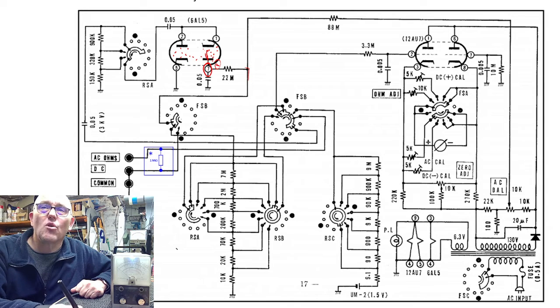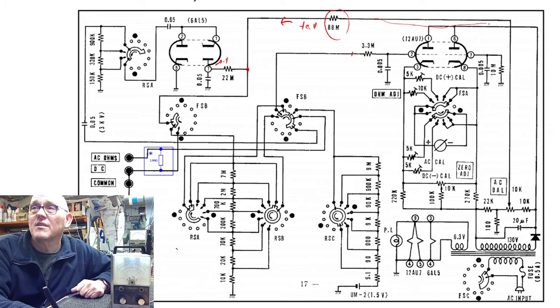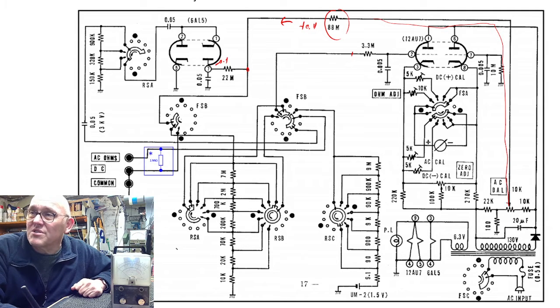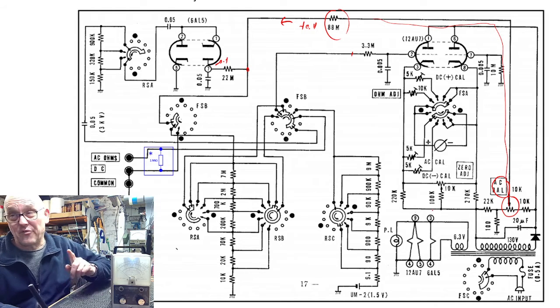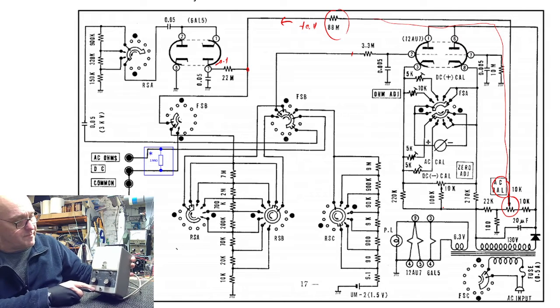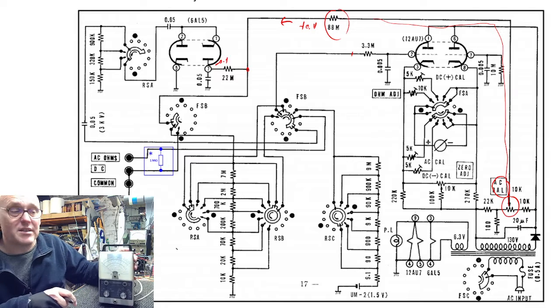So we need to offset that bit of negative voltage when there's zero input. Let's say that it's minus 0.1 volts. If we don't want to put minus 0.1 volts over here, we're going to have to offset it. So we're going to have to put plus 0.1 volts over here. And the way that it's done is through this 88 mega ohm resistor, taking some of the voltage generated by the power supply through these resistors over here. I told you that we're getting about a 40 plus something, plus 40 plus 80, I can't remember, plus 80 volts. But we rectified and we pass it through this chain of resistors over here, and on this AC balance potentiometer, which is on the front of the unit, at least on the Kyoritsu, or on the Heathkit, it's not there, it's in the back. It has to be done during calibration.